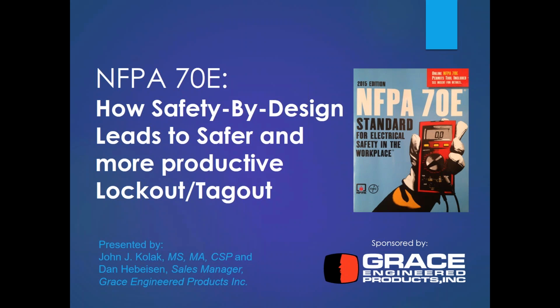The terms lockout, tagout, and energy control are synonymous. The OSHA standards we're going to be talking about are called energy control. With that said, we all refer to it as lockout, tagout, so that will be something to keep in mind as you read the slides. Also, there are three terms that are synonymous with each other: zero energy state, an electrically safe work condition, which you may recognize from Article 120 in the NFPA 70E, and the word dead. So we want to be careful to only use the word dead when we really mean dead, and we'll talk about how to get to that dead or zero energy state as part of the presentation.